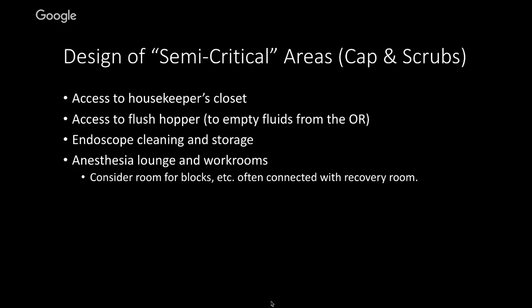In that same semi-critical area, the housekeeper's closet would be there because, of course, you will need janitorial services. This is where the nurses would have some access to some sort of flush hopper so that when they come out of the operating room with the fluids from the suction collections or the fluids from the back table, they have a place to flush these. You might have endoscope cleaning and storage here as well. And this is where the anesthesia lounge, the workrooms, et cetera, would all be in the semi-critical area. And of course, in the best of all worlds, you might actually have a separate room for anesthetic blocks, et cetera. And this would connect to the recovery room itself. Next, please.